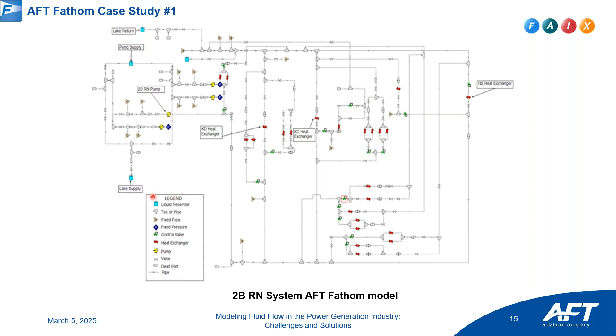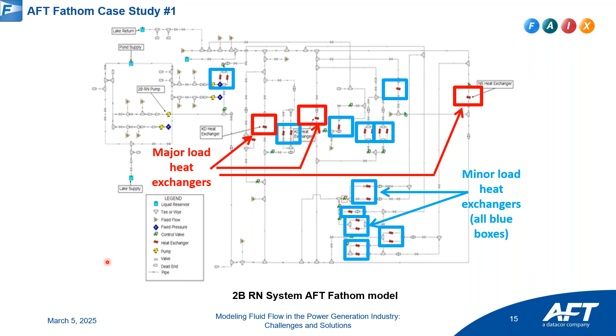Okay, the flow came in through the pump and had to provide cooling water to all of these heat exchangers. The red ones here are what we call the major load heat exchangers. Those are the most important and have the most flow. And then there were a bunch of minor load heat exchangers you can see down here where cooling water also had to be supplied. So the whole goal here was there were 3 different measurements for this system, and we were trying to take the piping in here and vary the pipe roughness and scaling to match the 3 measurement sets for this system, okay?